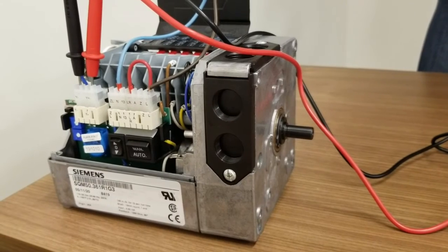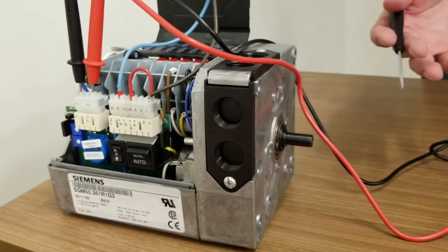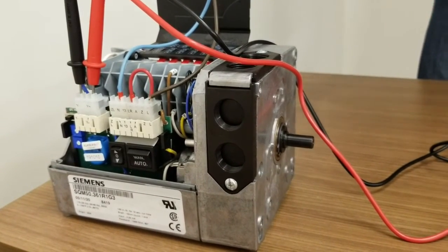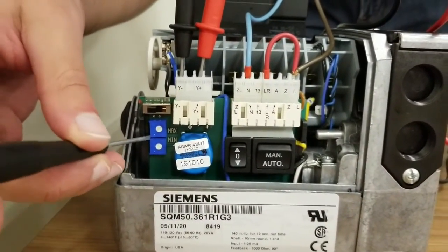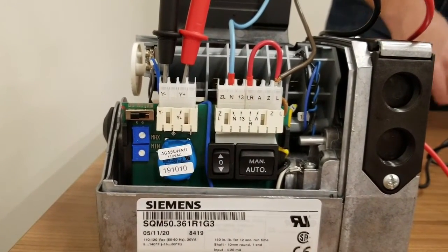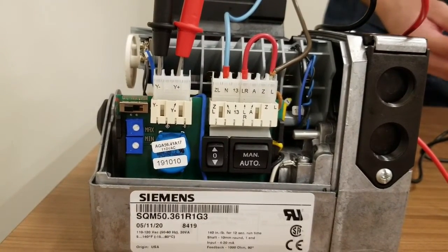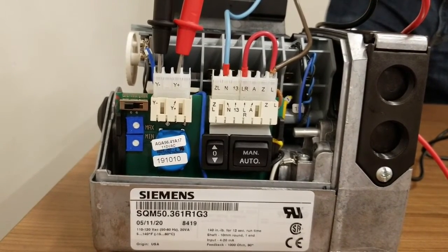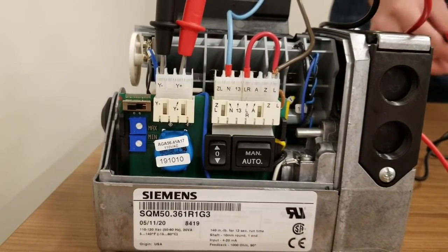Now that we've driven down to our low fire position, we want to ensure that we have a properly scaled input signal. We're going to use the same flathead screwdriver, and we're going to adjust the min potentiometer, the blue min potentiometer. This adjustment is going to ensure that we're utilizing the full range of the input signal. You're going to rotate the min potentiometer in a clockwise direction until the motor starts to drive slightly upwards.